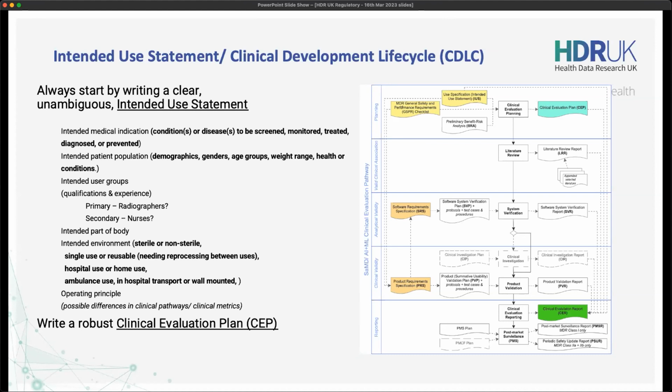From that, you derive requirements, which then say this is the performance, the accuracy you need, or something like this, in however you need to measure it. Some of it is regulatory. So say you go to the FDA, they have particular requirements about how you measure accuracy of radiology products, for instance. You figure out what are your product requirements from that, and then you engineer the release candidate for your software as a medical device.